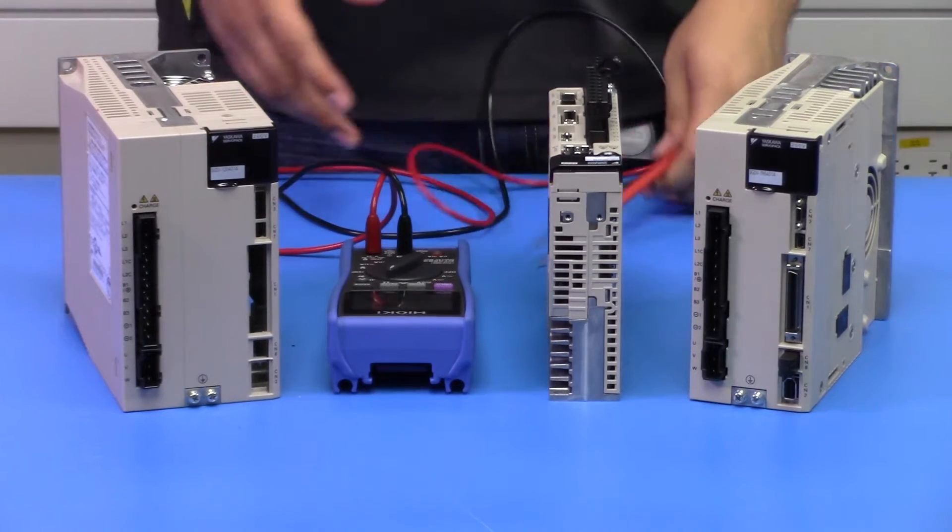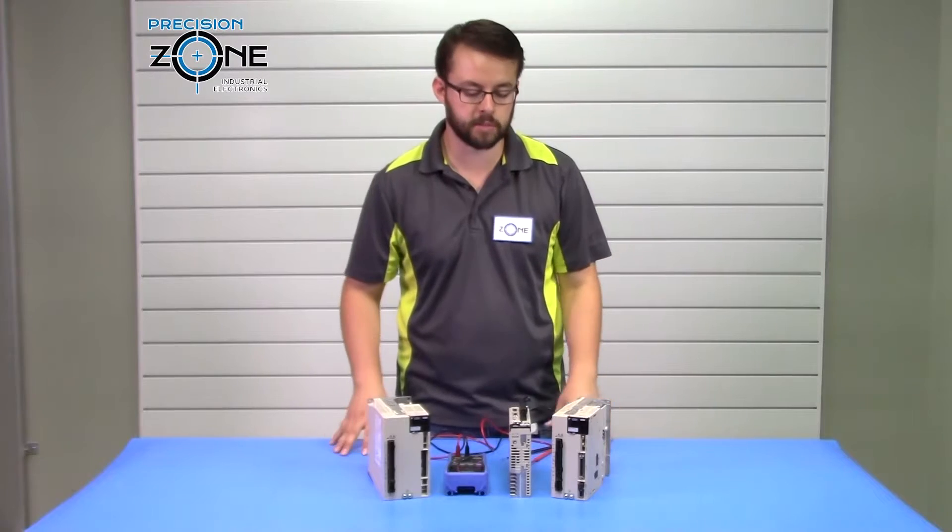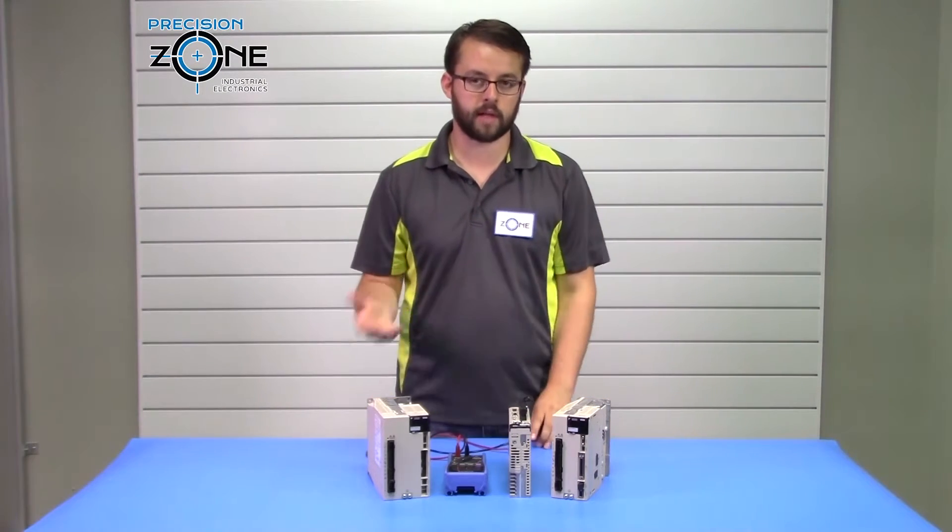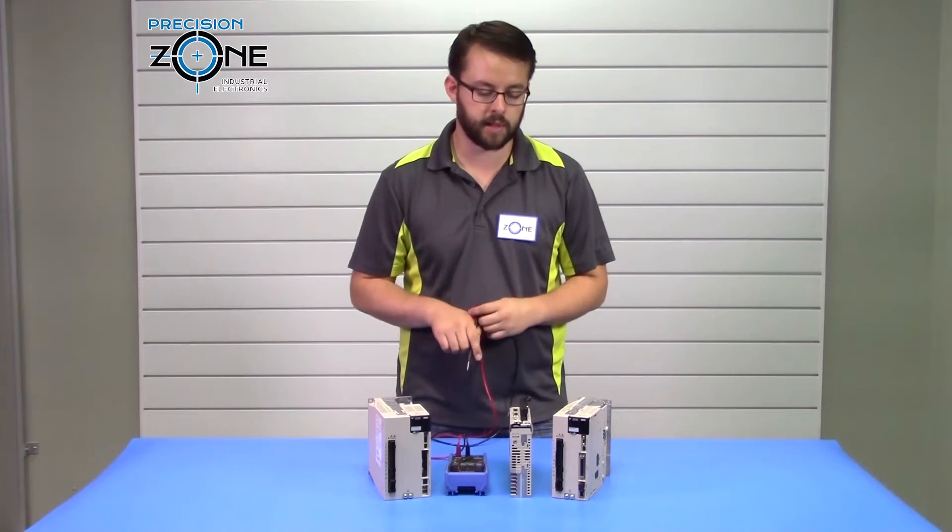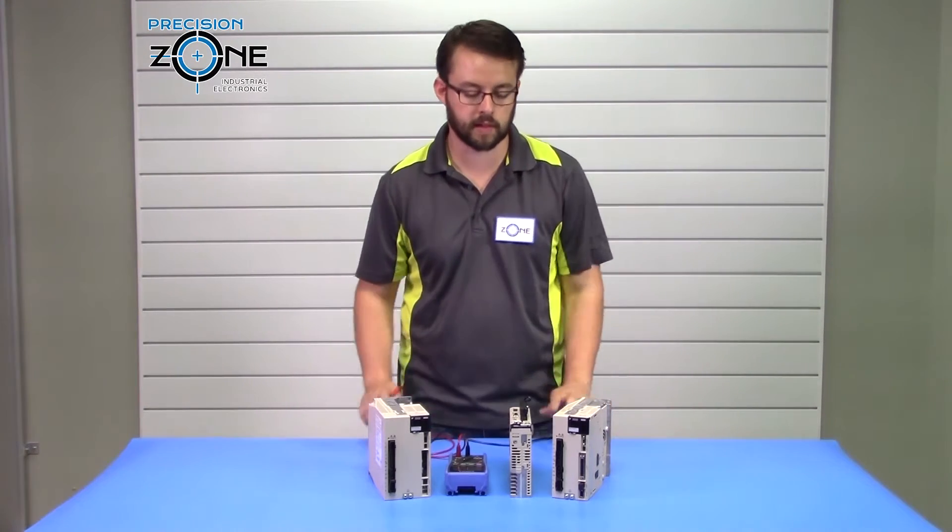To begin, you want to make sure that the drive has been disconnected from the machine and it has been powered off. You want to verify that it's been powered off for some time to make sure that the DC bus has been fully discharged to prevent any accidental shocks.